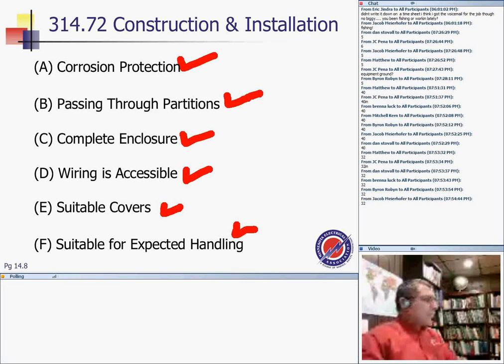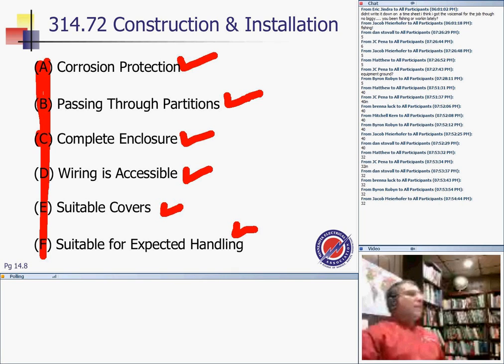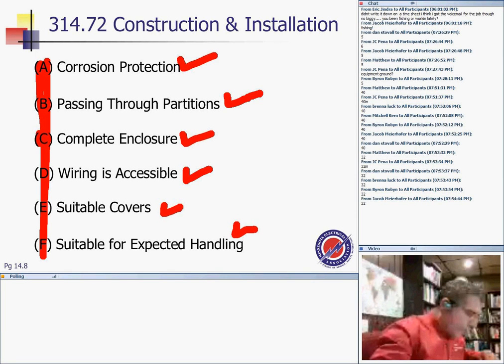So that these cables, you love them and make sure they're going to be there 5, 10, 15 years from the installation. And these pull boxes for medium voltage, higher than 600 volts, the only thing about them is how they size them. They size them based on the diameter of the conductor, not the conduit like we do in the low voltage.